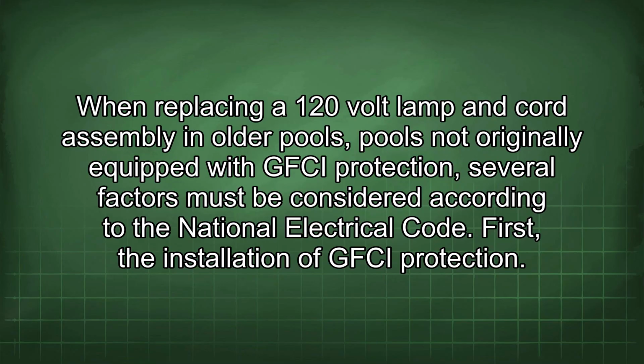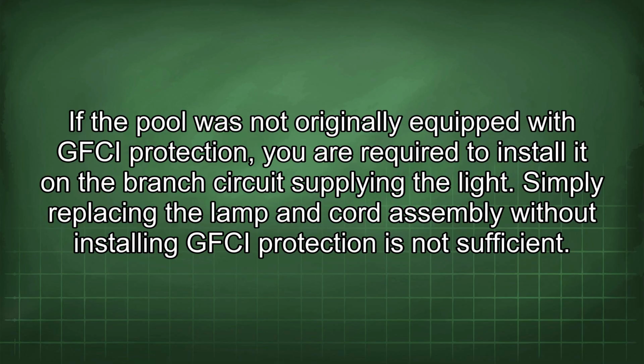When replacing a 120-volt lamp and cord assembly in older pools not originally equipped with GFCI protection, several factors must be considered according to the National Electrical Code. First, the installation of GFCI protection. If the pool was not originally equipped with GFCI protection, you are required to install it in the branch circuit supplying the light. Simply replacing the lamp and cord assembly without installing GFCI protection is not sufficient.